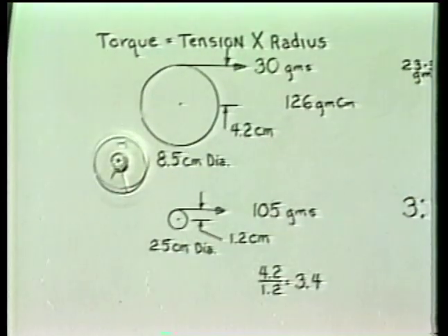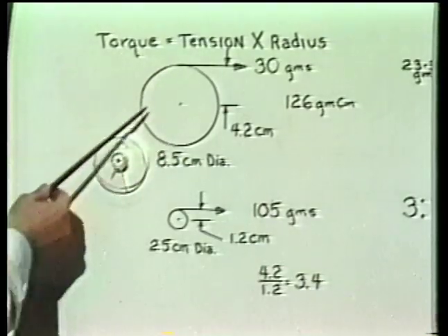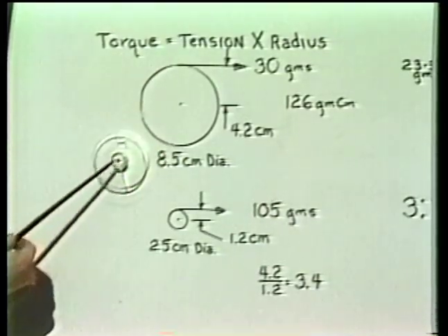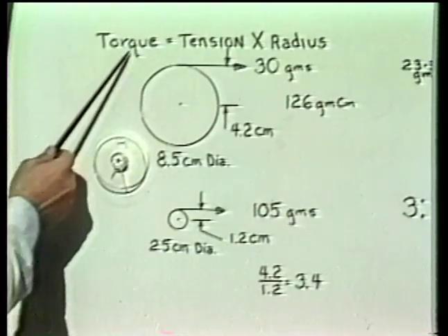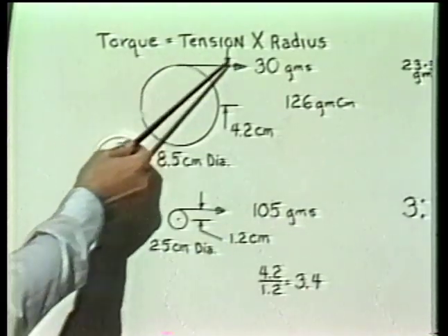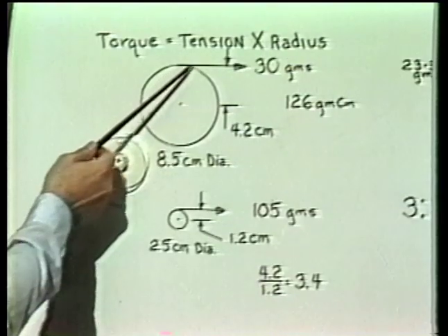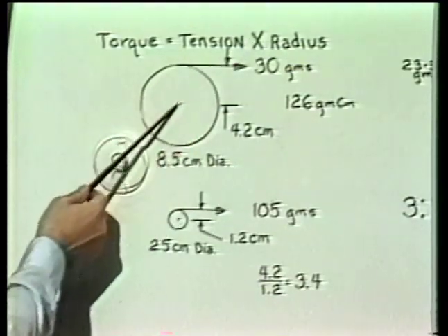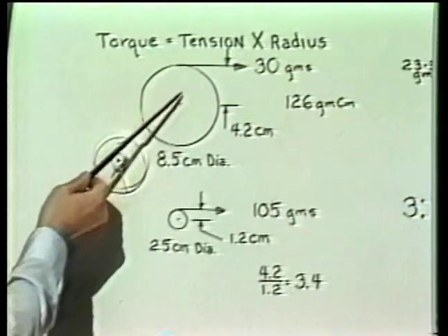We thought a brief review of the terms torque and tension would be useful, since some of the factory service manuals seem to use these terms interchangeably. As we'll show, they really aren't interchangeable terms. Torque, when it's related to a round reel like we're using in a tape path, equals the tension exerted on that tape path by the tape times the radius, which is half the diameter, of that particular reel.